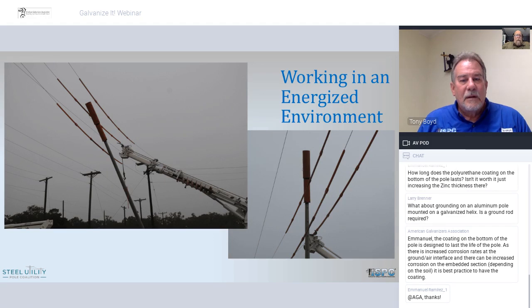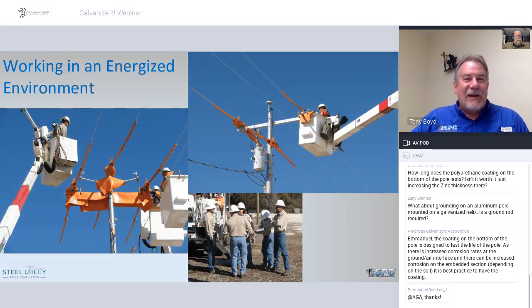As the pole butt comes down to the location where the pole is going to be set, a lineman there with a shotgun holding the cable in the end of the shotgun simply reaches up, and the magnet clamps itself to the pole and thereby grounds the pole, to provide a level of safety for setting the pole in that energized environment. Go ahead, Tony. I think you said it all. Moving along to the next slide.